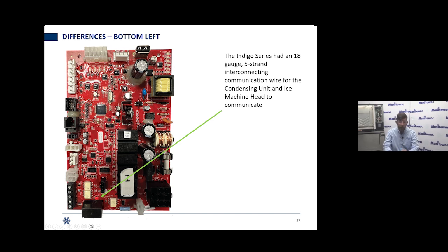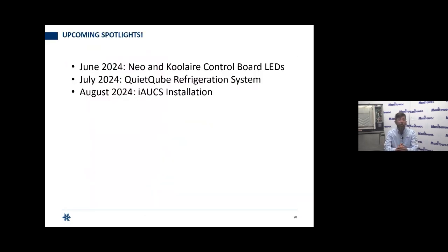For those of you who have come through trainings and through the factory school, we highlight what this light is doing. You want to use this light in coordination with a working display, so that way you can see, hey, I'm in freeze and this light isn't lit. Well, that lets me know something in the low pressure circuit told the board that the low pressure switch opened. If the high pressure circuit had opened outside on an Indigo, the home screen would say HPCO active delay and give you a 60-minute countdown. The light, the relay, and the communication wire are only present on Indigo. They are not present on Indigo NXT. So that's how the LEDs on our control boards for the Indigo and Indigo NXT work.